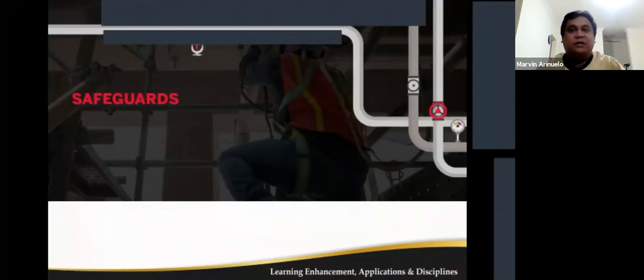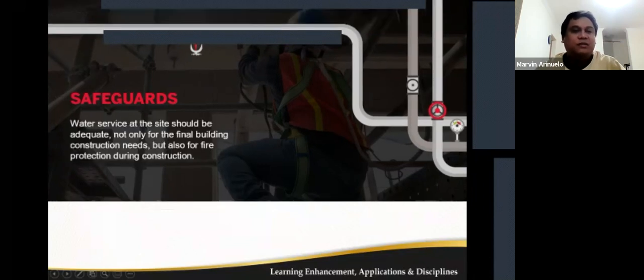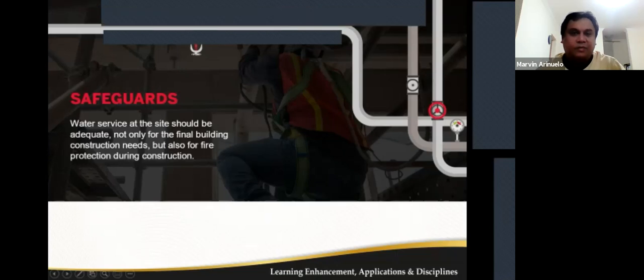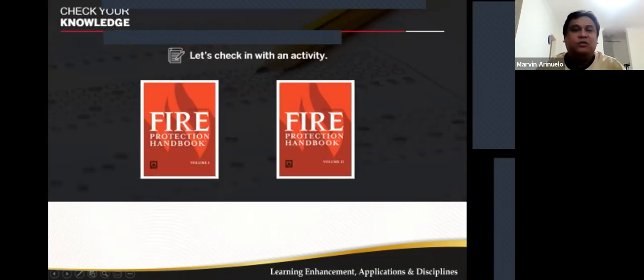So now let us discuss the safeguards. The water service at the site should be adequate, not only for the final building construction, but also for fire protection during construction. In a multi-story structure, either temporary or permanent, the standpipe should be put into service as each floor is constructed to provide firefighting capability. In a building without automatic sprinklers, the installation of water tanks and other fire protection equipment must wait for the completion of the structural elements. This standpipe and hose system may provide the only reliable source of water for firefighting during the construction of the project. So let's check in with an activity using your fire protection handbook.